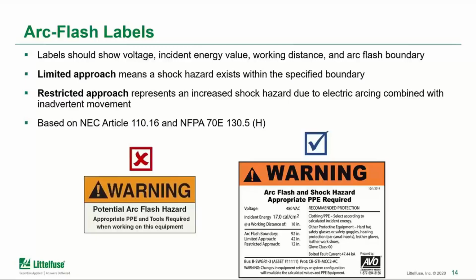So that label that's on the left, while it does give a warning that there is an arc flash hazard, it doesn't give you the information needed to then come back and have a safe work practice or safe work procedure based on that information. So the label needs, of course, to show things like the voltage, the incident energy, the working distance, and the arc flash boundary, and those are defined by NFPA 70E. There's a clause shown on the screen.